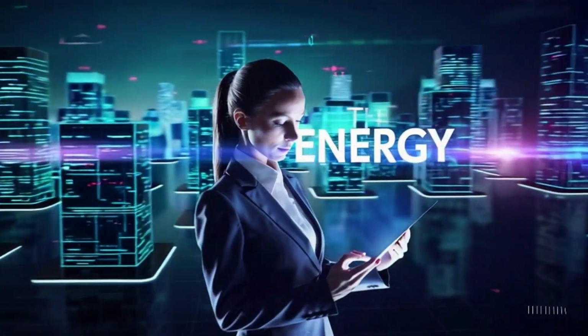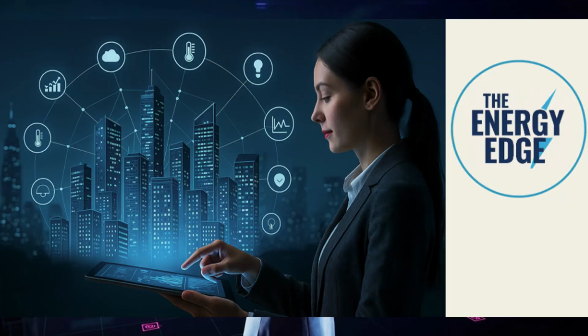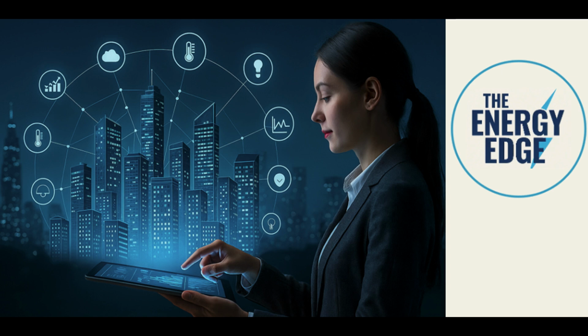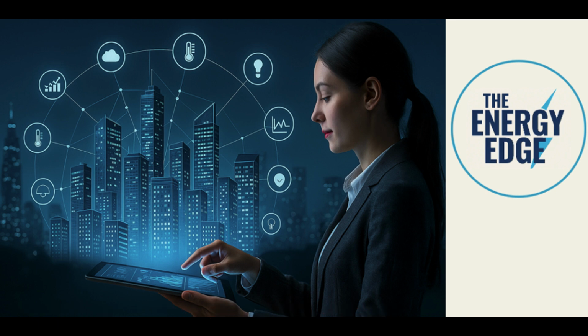Today we're digging into airside economizers. Right. Think of this as your quick guide to how these systems use outside air to cool buildings and save energy, of course. Exactly. Free cooling. That's the core idea you'll see in standards. So free cooling, basically letting nature do the work when the weather's right. Precisely. They bring in outside air, provided its temperature and humidity are suitable, to help out the cooling load, sometimes even handle it completely. It cuts down on running the main AC.